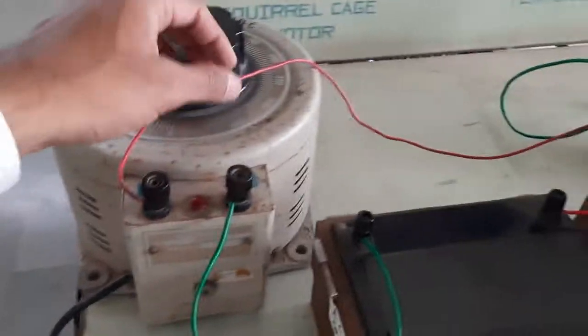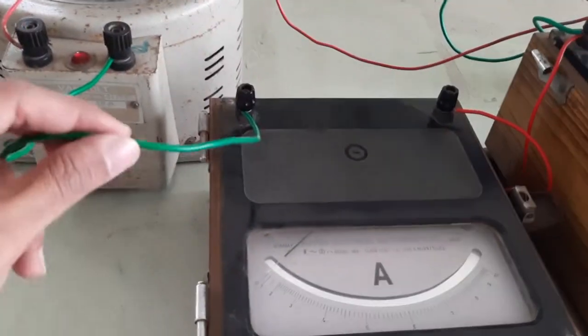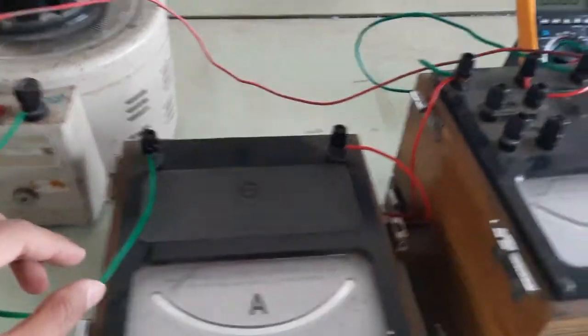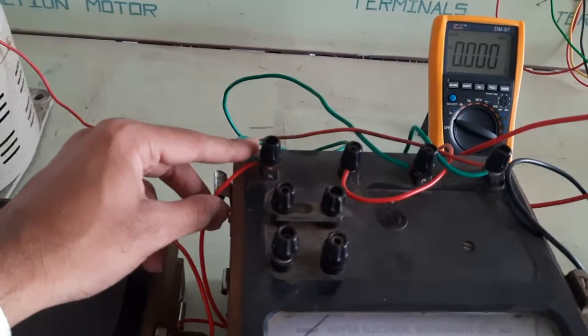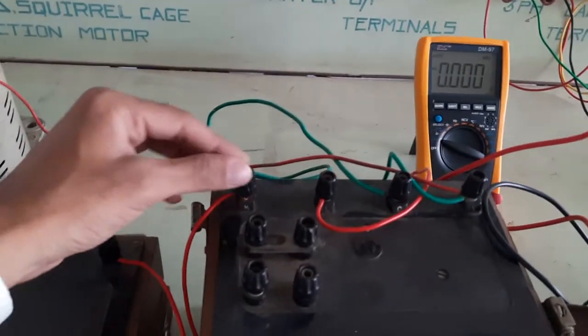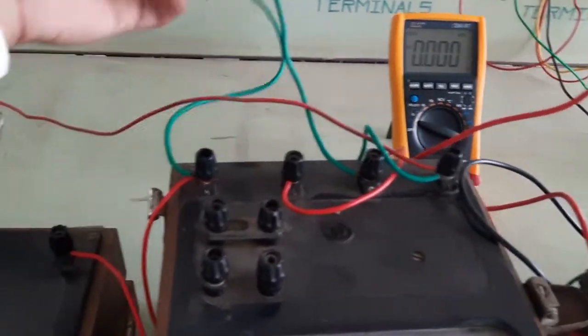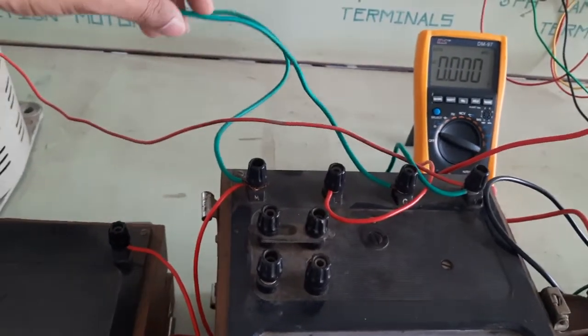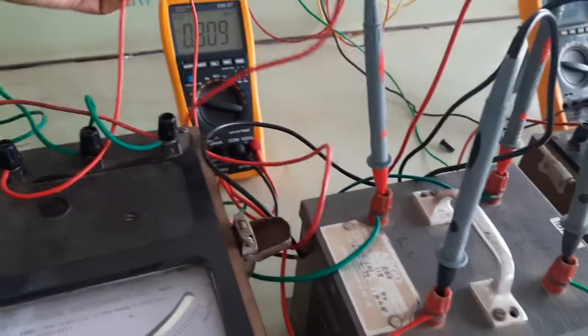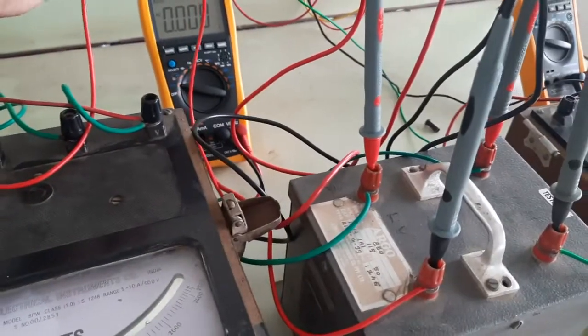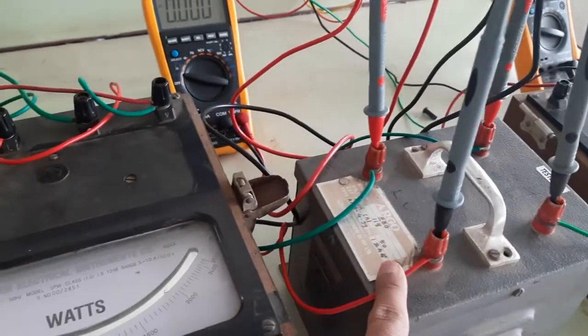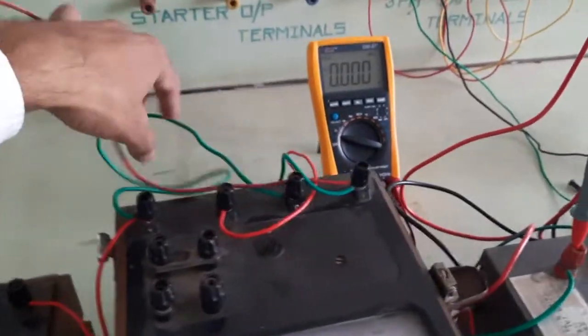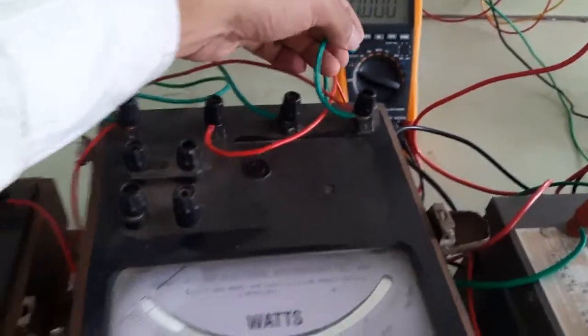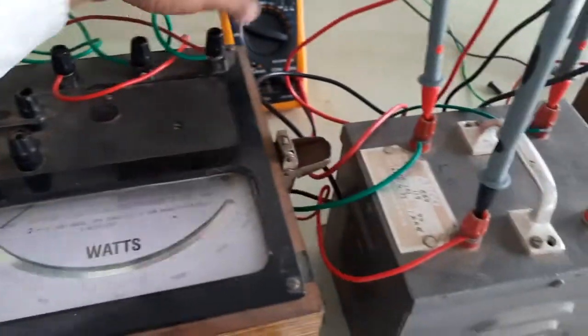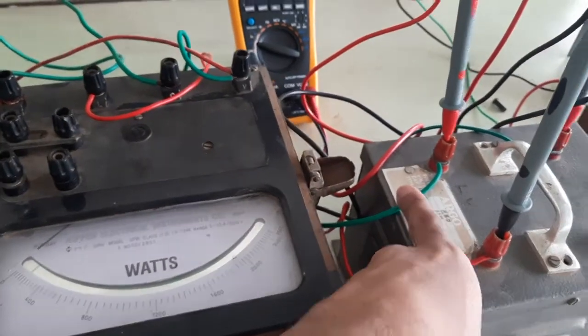The positive is connected to the input of the ammeter on the primary side. After the ammeter, it is connected to the M terminal, M for mains. Then M and C are always shorted. Then the L terminal is connected to the input of the primary of the transformer. Then the neutral terminal is connected to the V of the wattmeter, and then to the primary connection of the transformer.